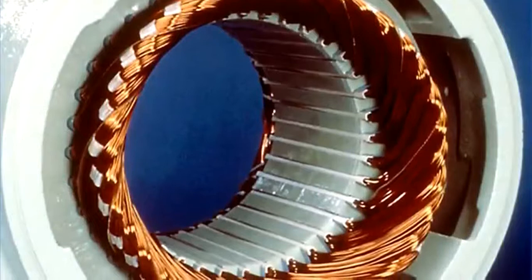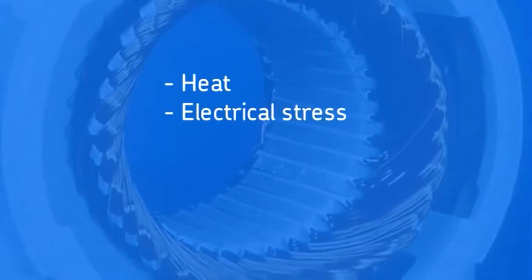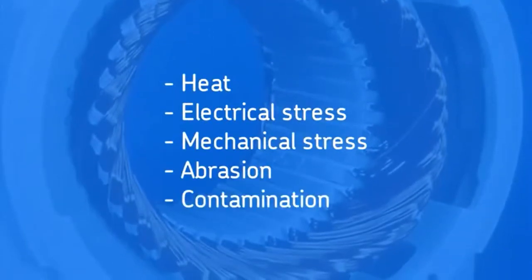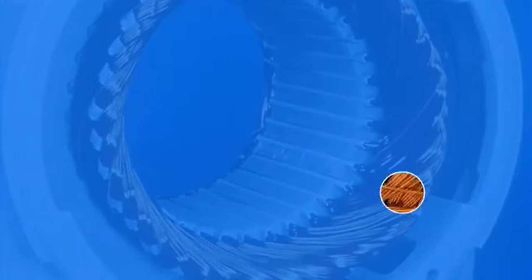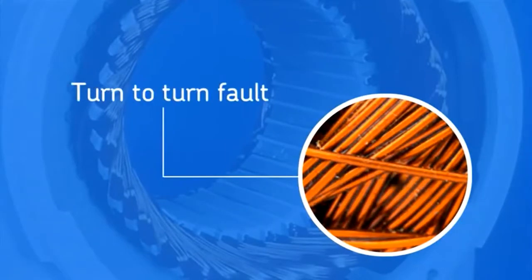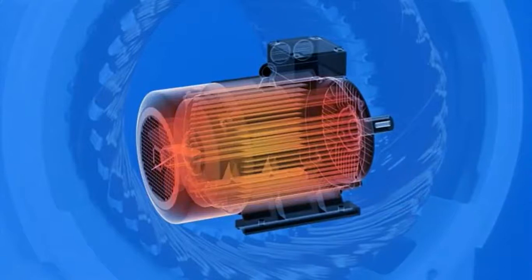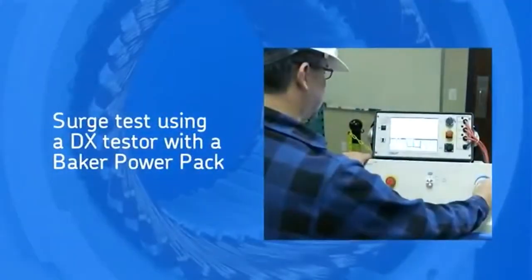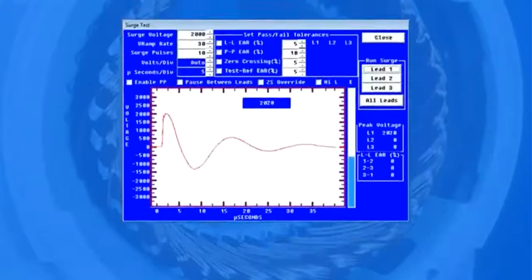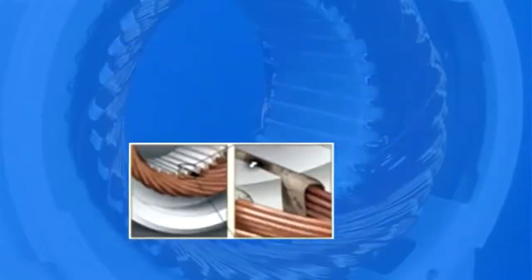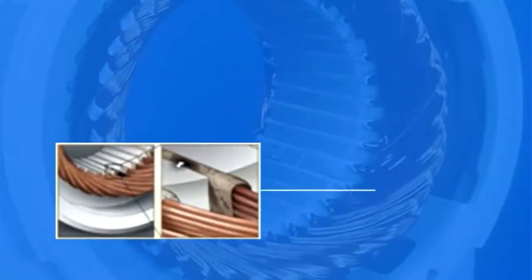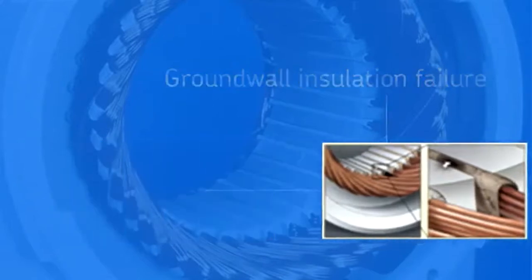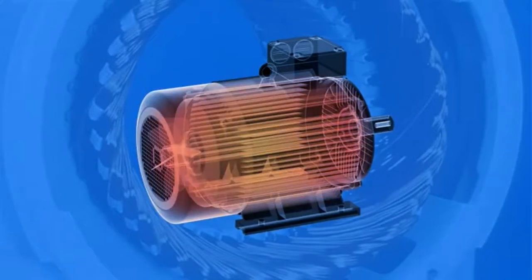The stator insulation is most prone to failure. Insulation strength degrades over time due to heat, electrical stress, mechanical stress, abrasion and contamination. The most common insulation failure is between turns of wire that are next to each other in the same coil. This is called a turn-to-turn fault. When this fault occurs, the motor will draw a lot of current, quickly overheat, and can melt down in minutes. The surge test can reliably find the strength of turn-to-turn insulation, giving you early warning about when the insulation is weak. When the insulation fails and there is a path to the core, it is called a ground-wall insulation failure, since the stator core is at electrical ground. Oftentimes when a motor overheats or has a turn-to-turn failure, the excessive heat will cause a ground-wall insulation failure also.